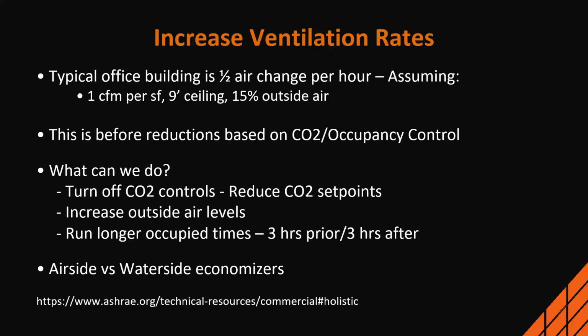So if we're doing a new system, this is going to gear which direction we're going to go on some of our system selections. If I have an air side economizer, I get 2 benefits out of it. I can run up to 100% outdoor air because of the ventilation. And when I'm in economizer mode, I am running 100% outdoor air, and therefore I'm getting full flush through my building.